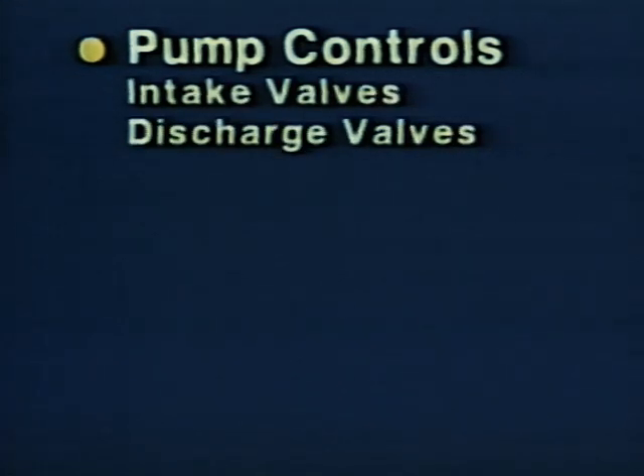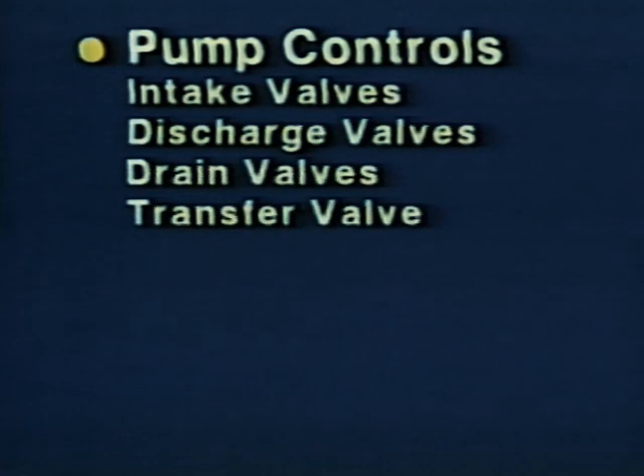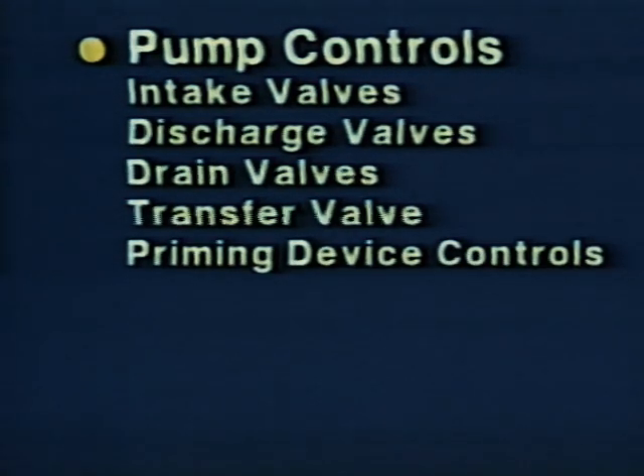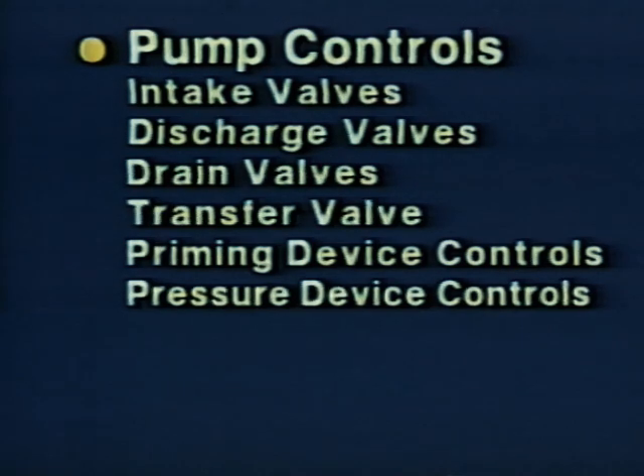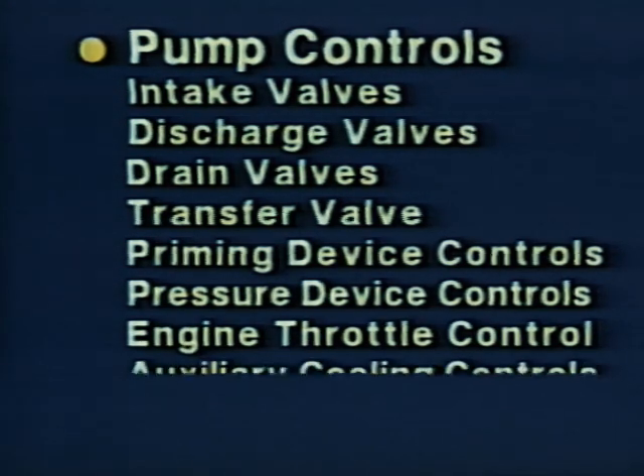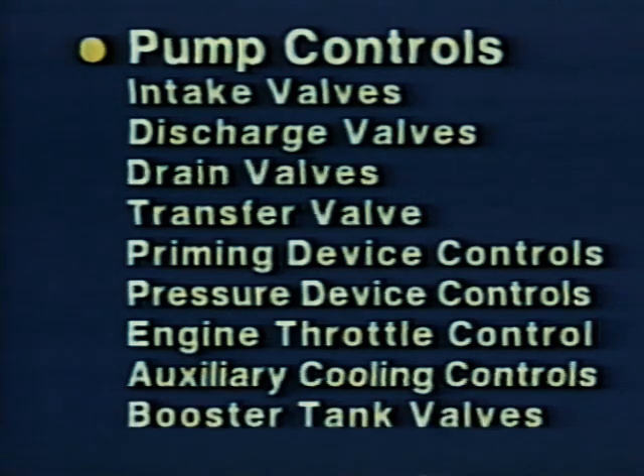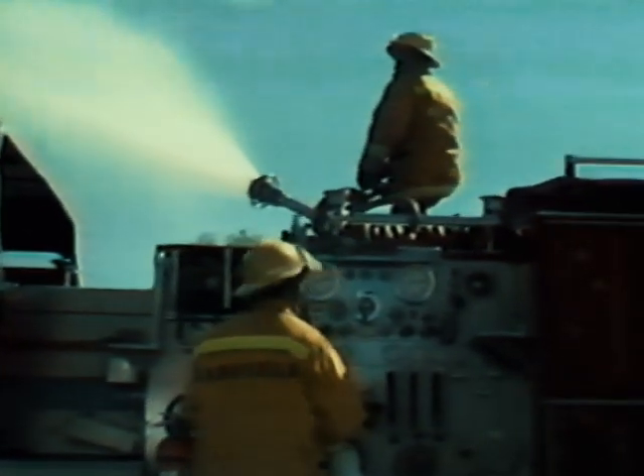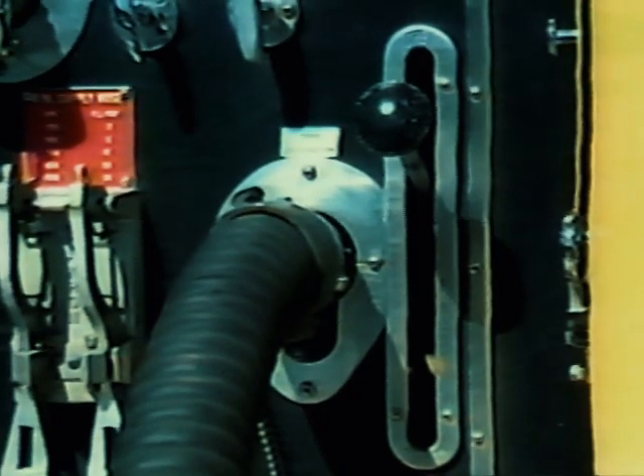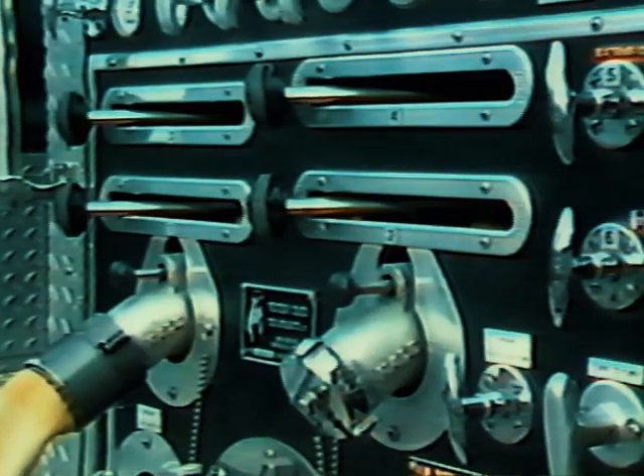Controls for operating the pump usually include intake or discharge valves, drain valves, a transfer valve on an apparatus with a multi-stage pump, controls for the priming device, controls for the pressure control device, engine throttle control, controls for the auxiliary cooling system, and controls for the booster tank. The intake and discharge valves on a fire pumper control the flow of water entering or leaving the pump during a pump operation. Intake valves control the water entering the pump. Discharge valves control the water leaving the pump.